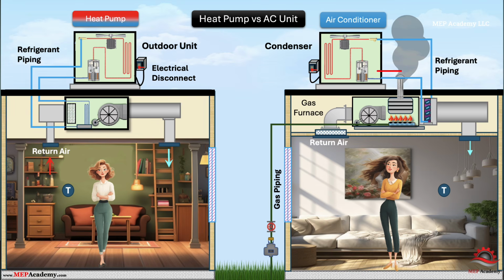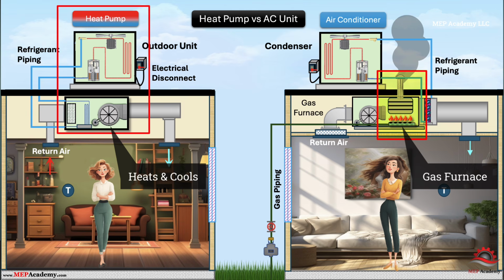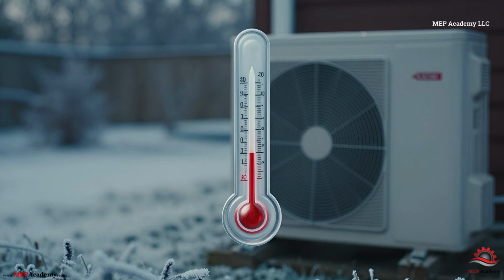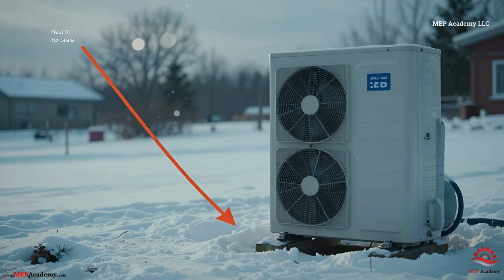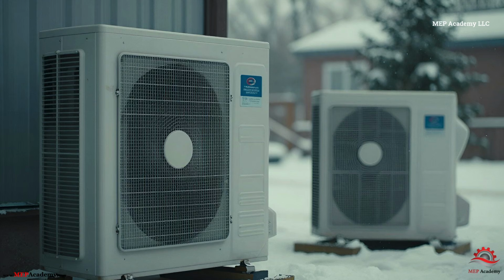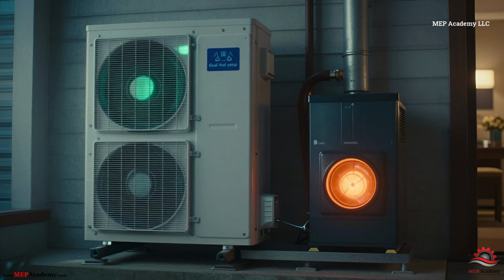Air conditioner requires a furnace or electric heater for heating. Heat pump provides both heating and cooling. This is the biggest functional difference. Heat pumps can reach efficiencies of 200% to 400% in heating mode because they move heat rather than generate it. But that performance is highly dependent on outdoor air temperature. As temperatures drop, efficiency declines, and in colder climates, a high-efficiency gas furnace can outperform a heat pump in both capacity and reliability. This is why many systems use a dual-fuel setup: a heat pump for mild temperatures and a gas furnace for colder conditions.